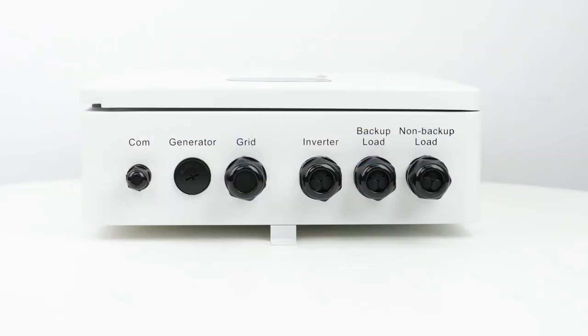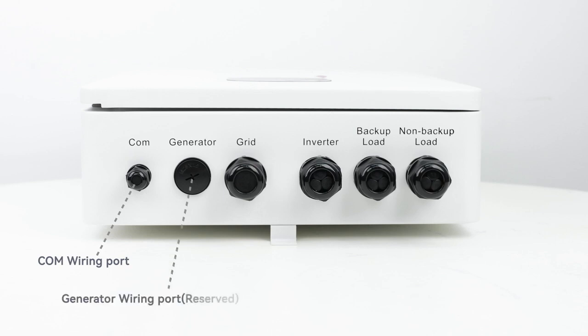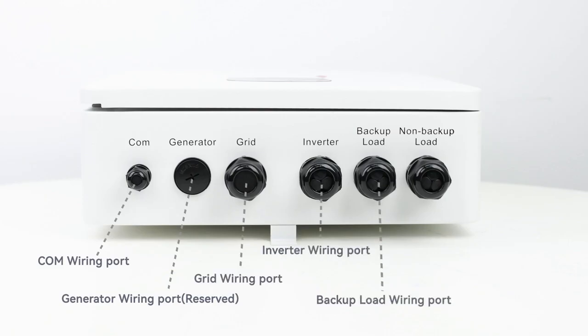This is all the ports of the SYN. The ports from left to right are COM wiring port, which is for communication of external meter and inverter. Generator wiring port. Noted, SYN50XH10 does not support the generator function. Grid wiring port. Inverter wiring port. Backup load wiring port, which can be connected to critical loads in the home to keep them going during grid power outages. Non-backup load wiring port. The maximum output of this port is 6 kW.